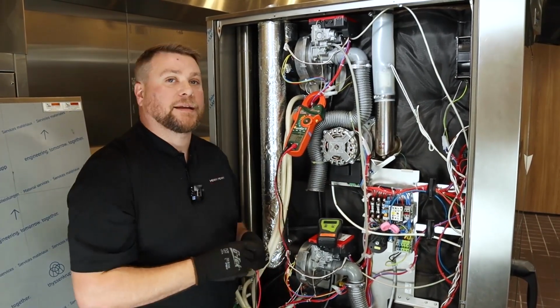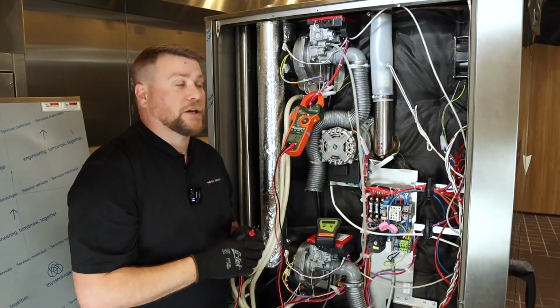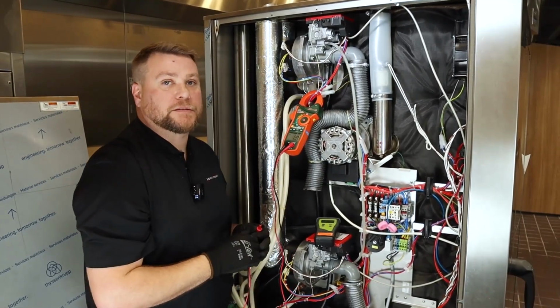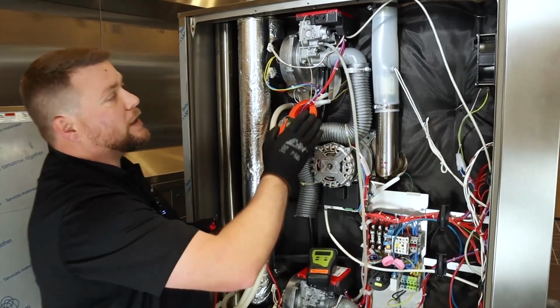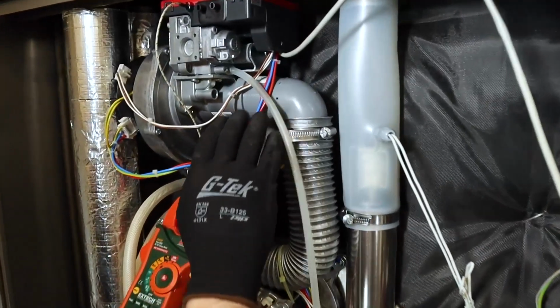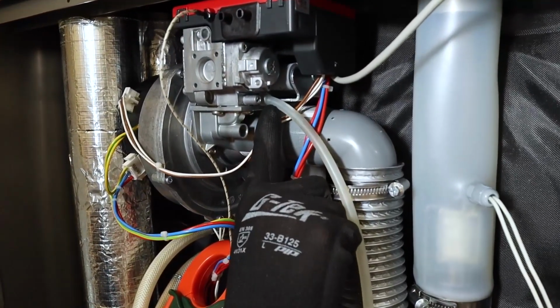So I'm going to check the dynamic pressure, but at the same time I'm checking that, I'm also going to check my flame sense. So to go ahead and hook up my manometer to the gas valve, you'll see that I'm on the right side port here.